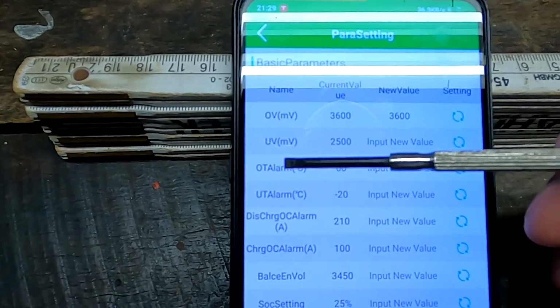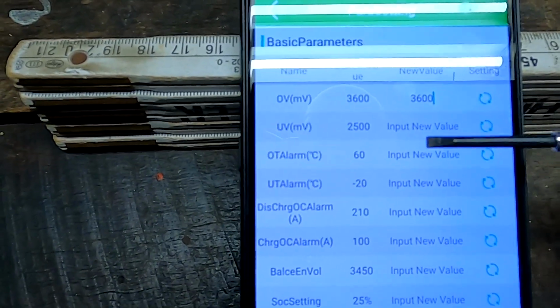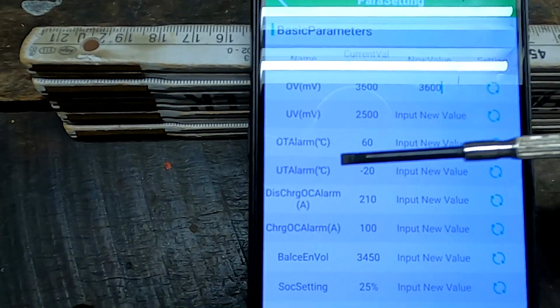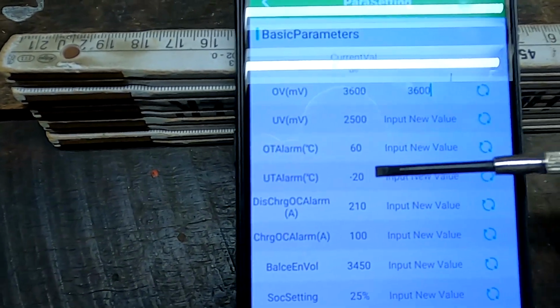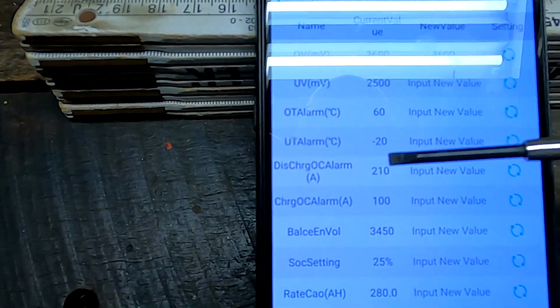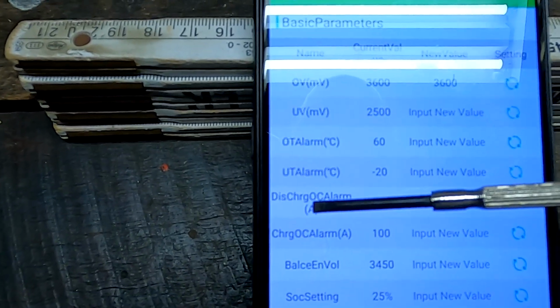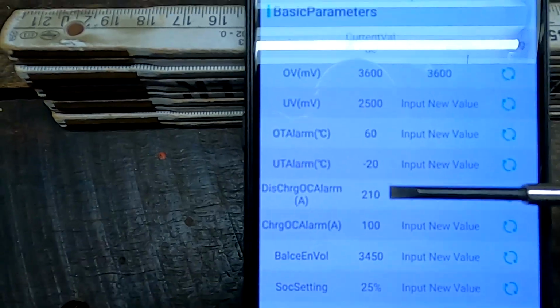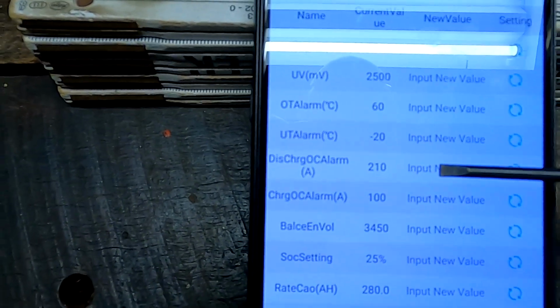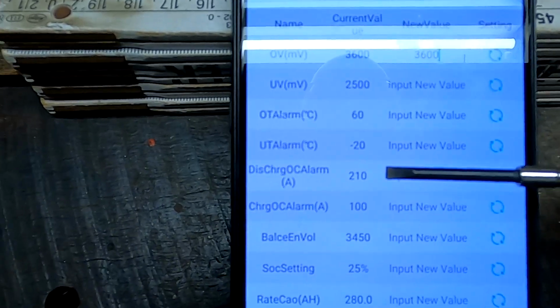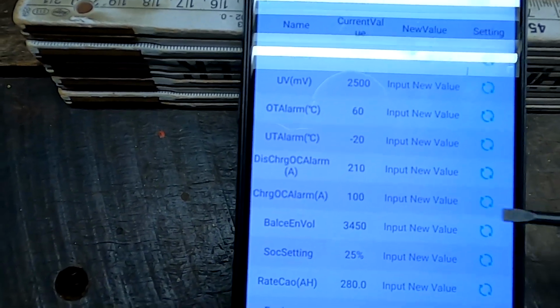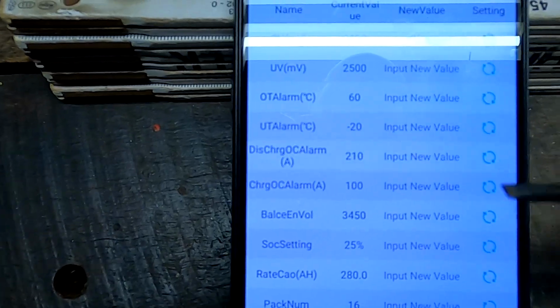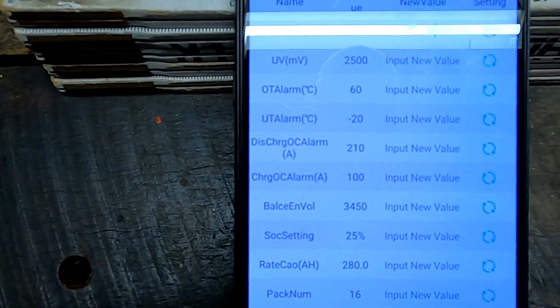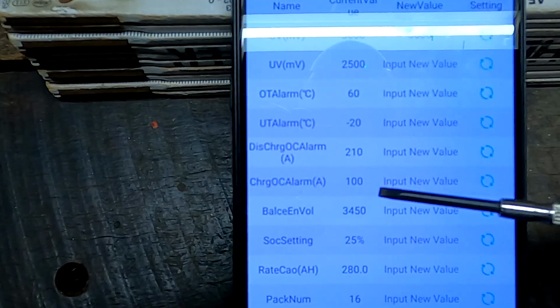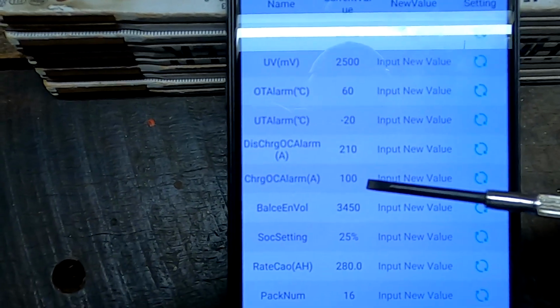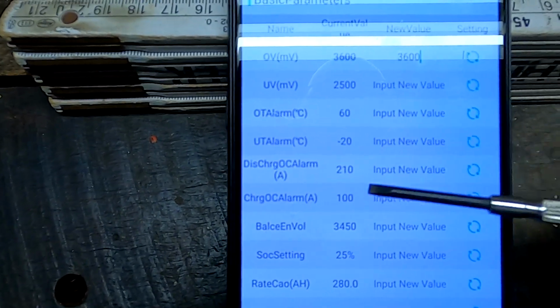The over temperature alarm is 60 degrees, but again you can change this to your needs. Under temperature alarm -20, you can change this. Discharge over current alarm - so this is the maximum current you can pull out of this BMS, which is 210 amps, this is the standard default setting. It's a 200 amp BMS. The charge over current alarm sits on 100 only, and I thought this is a bit weird because it's a 200 amp BMS.